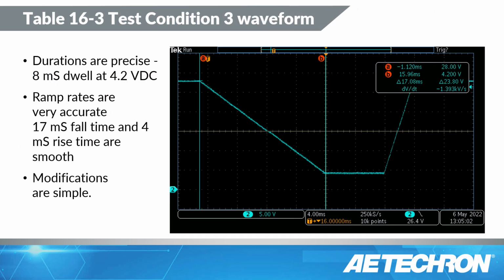I set this up in the 3110 signal source with an amplifier to perform this test. And here are the results. Now, there is my 17 millisecond decay time. And if you notice, that is a very smooth waveform. It isn't stair-stepped at all. It is very, very continuous. And then I have at 4.2 volts my 8 millisecond dwell and a 4 millisecond rise. Now you'll notice down here, this is 4 milliseconds per division. So there's 2 divisions here, 1 division there. And you'll notice right there, I've got my markers showing a 17 millisecond fall time to 4.2 volts. So very precisely performed and very clean waveform.